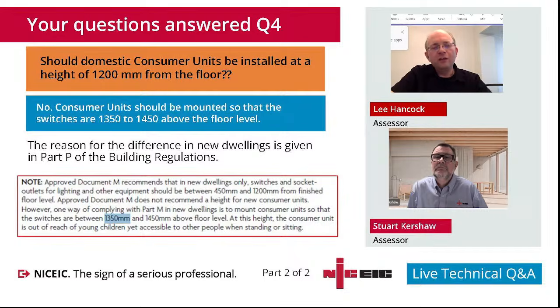The reason it's slightly higher than the light switches, which are at 1200, is that we've got to consider children. We want children to operate light switches, socket outlets and the like safely, but we don't want them interfering with the consumer unit. So it's accessible for somebody who's possibly disabled, or in a wheelchair, but maybe it's not quite as easily accessible for a small child, if that makes sense. So they're not liable to, for instance, operate the main switch and put the place into darkness just through playing about. Yep. Thanks, spot on, Lee.